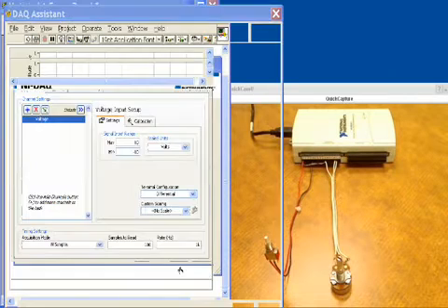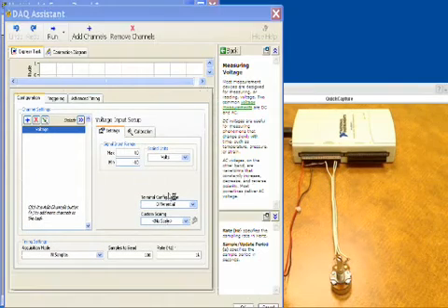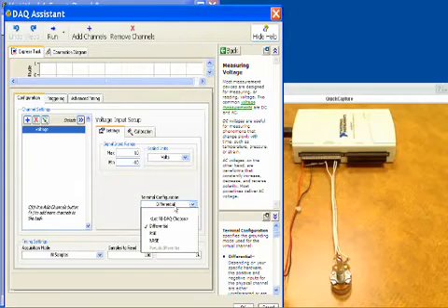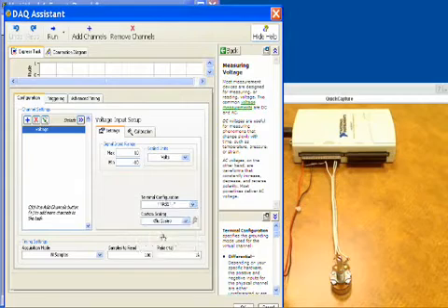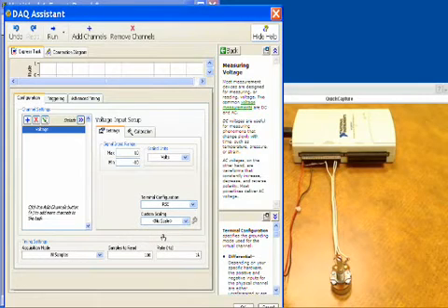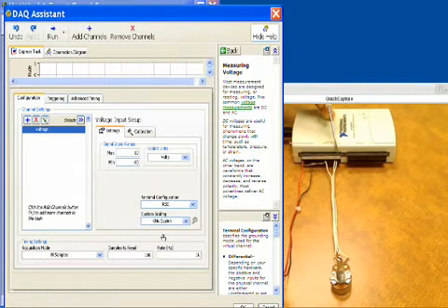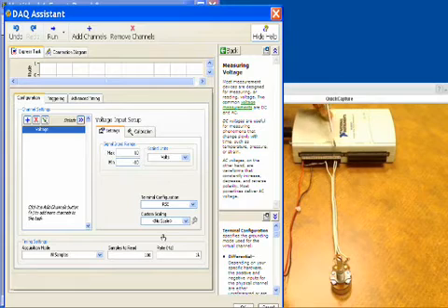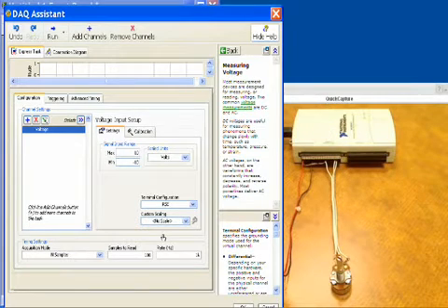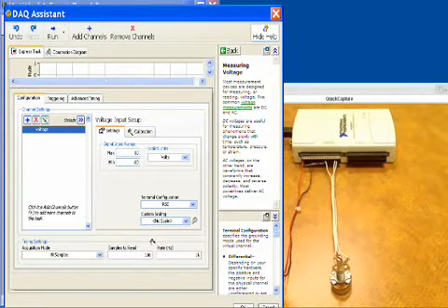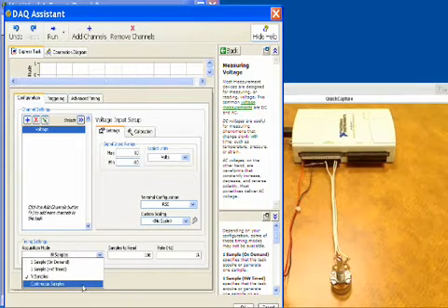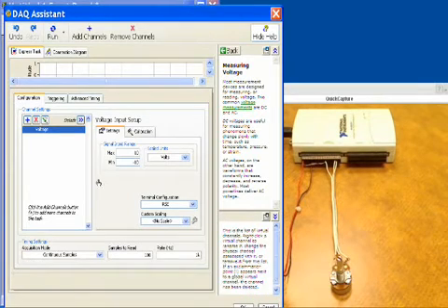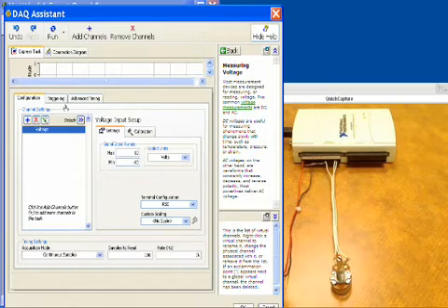What we need to do now is specify some things about this acquisition. I know that my input is reference single ended because I'm just using one input and then the ground here on my system as the negative side input. I also need to tell it to acquire data continuously so that it runs over and over again and that it is gap free.